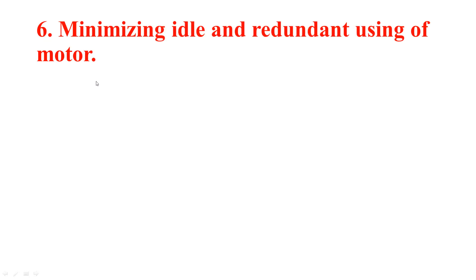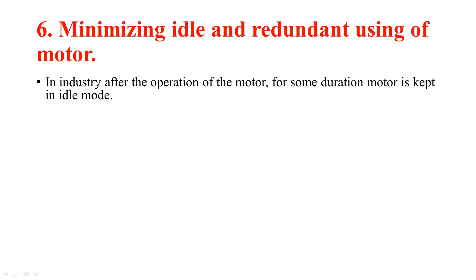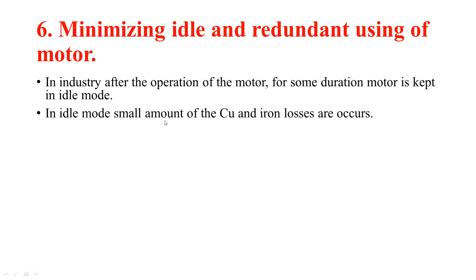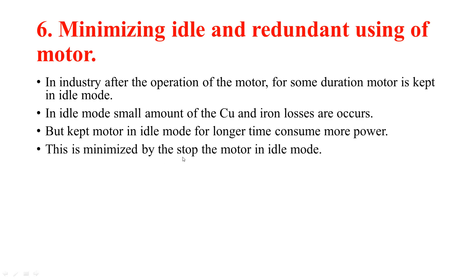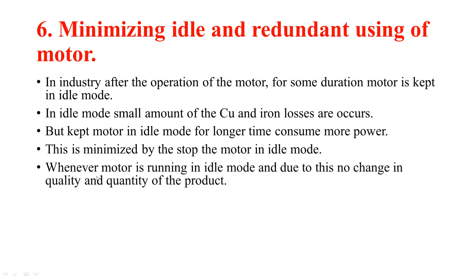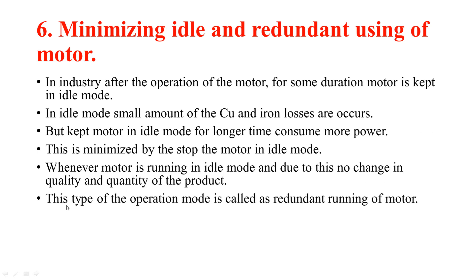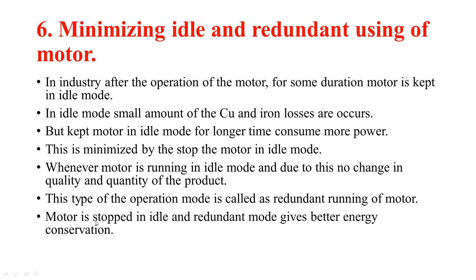Point number six is minimizing idle and redundant operation of the motor. In industry, after the operation of motor, for some duration the motor is kept in idle mode. In idle mode, a small amount of copper and iron losses occur. But keeping the motor in idle mode for a longer time consumes more power. This is minimized by stopping the motor in idle mode whenever there is no change in quality and quantity of the product. This type of operation is called redundant running of the motor. Stopping the motor in idle and redundant mode gives better energy conservation.